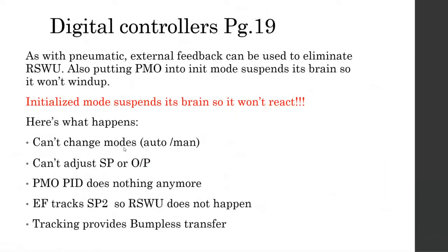Digital controllers. As with the pneumatic controllers, external feedback is used to eliminate reset windup. Also, putting the primary into an init mode suspends its brain, so it won't wind up. That's a phrase that I use. When you put it into an init mode, it basically doesn't want to do anything. It's waiting for some other permissive to happen before it can do anything. So an initialized mode suspends its brain so it doesn't react.